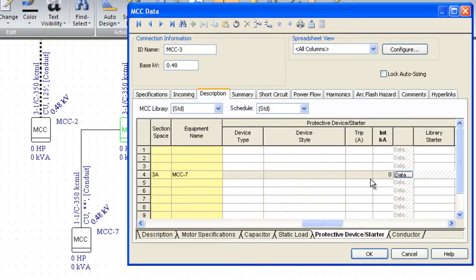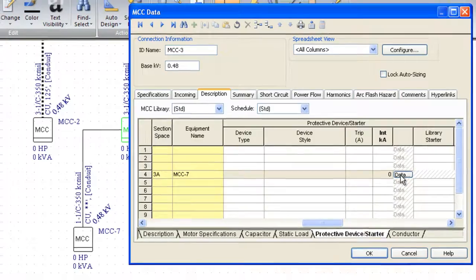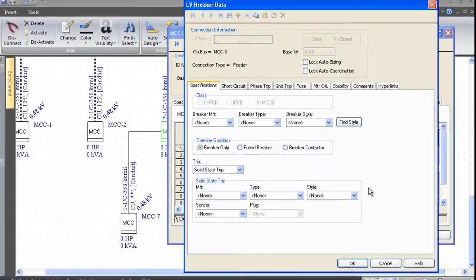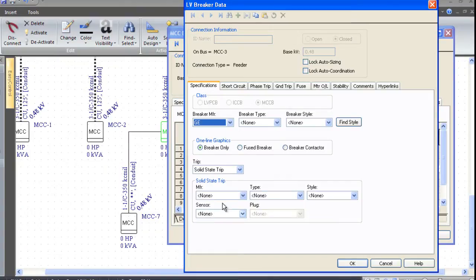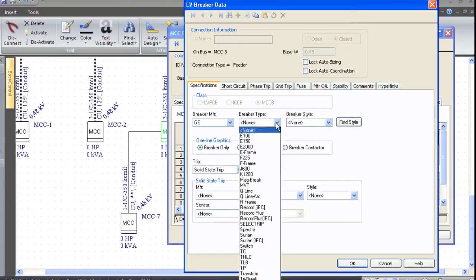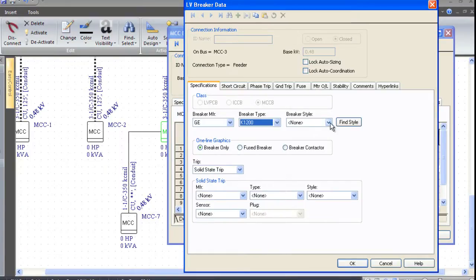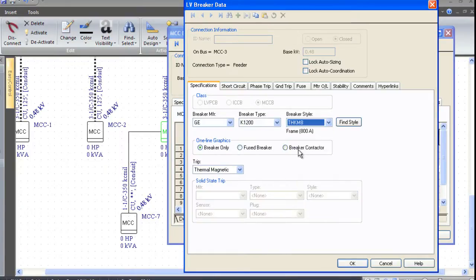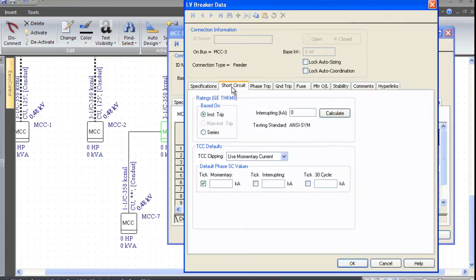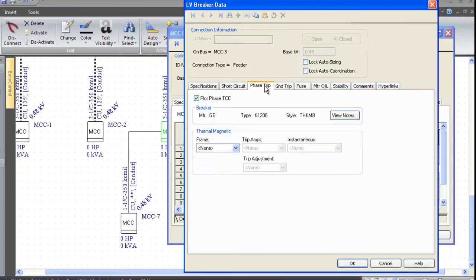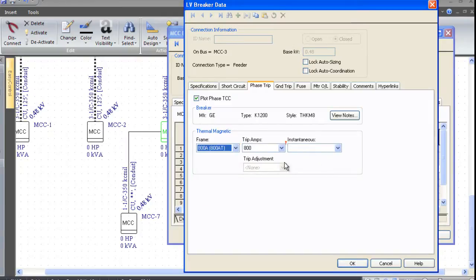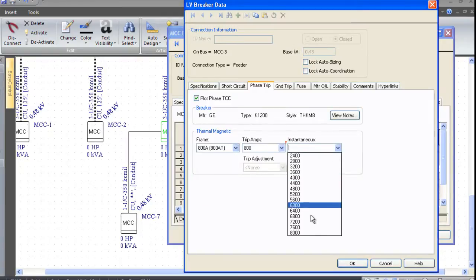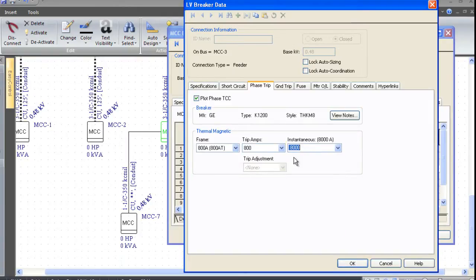You can see that here is the little data button for MCC-7. I can press this button, and it will allow me to pick, say, a General Electric K1200 frame THKM8 breaker. It tells me it's thermo-magnetic. It's rated for 35 kiloamps, and I've got a phase trip setting of say 800 amps and an instantaneous of 8,000.